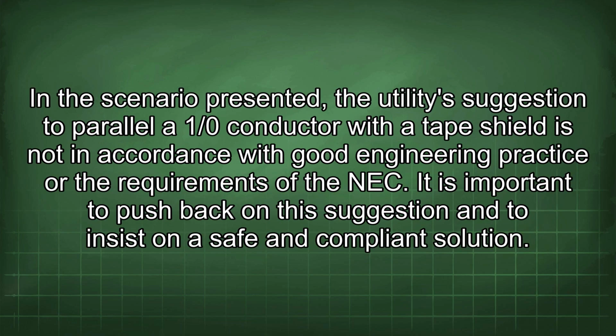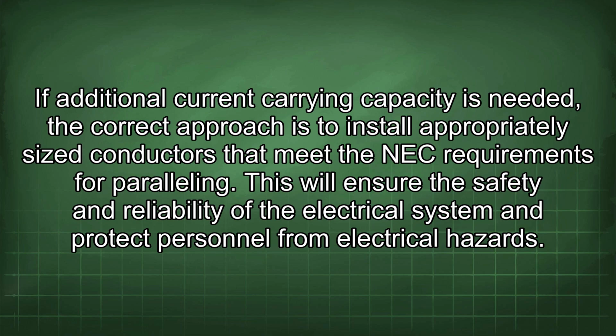In the scenario presented, the utility's suggestion to parallel a 1/0 conductor with the tape shield is not in accordance with good engineering practice or the requirements of the NEC. It is important to push back on this suggestion and to insist on a safe and compliant solution. If additional current carrying capacity is needed, the correct approach is to install appropriately sized conductors that meet the NEC requirements for paralleling. This will ensure the safety and reliability of the electrical system and protect personnel from electrical hazards.